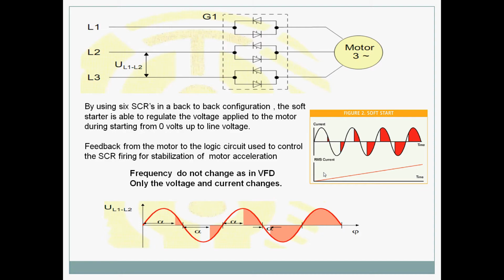Now, by using 6 SCRs in back-to-back configuration, the soft starter is able to regulate the voltage applied to the motor during starting from 0 volt to the line voltage. The feedback from the motor goes to a logic circuit used to control the SCR firing and stabilize motor acceleration. Frequency does not change as in a VFD. In a variable frequency drive, you have heard that the VFD works on the basis of changing the frequency of the motor or supply line. Here the frequency is not changing. The only thing that is continuously changing is the firing angle.